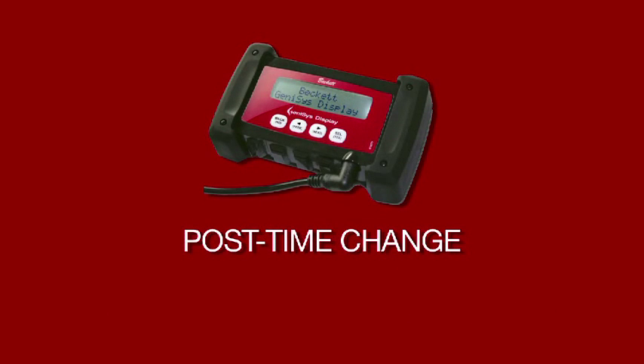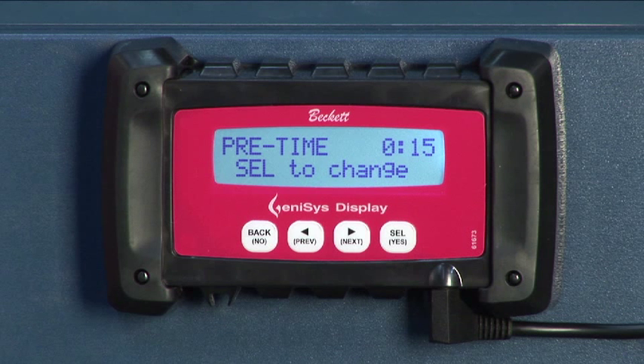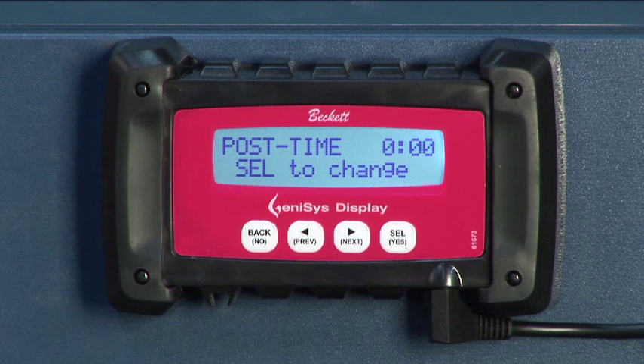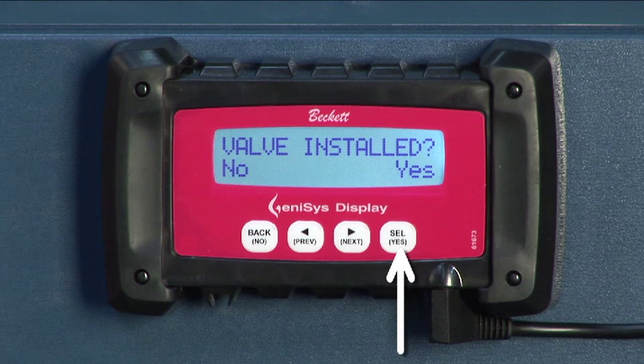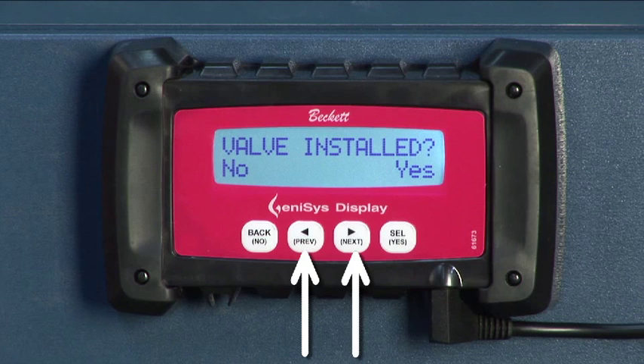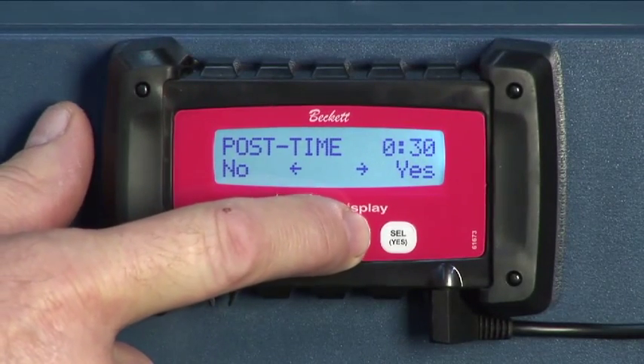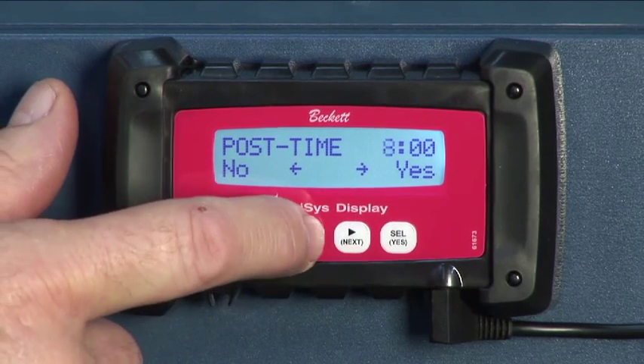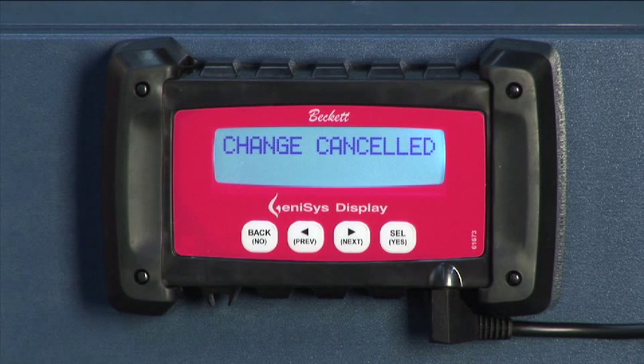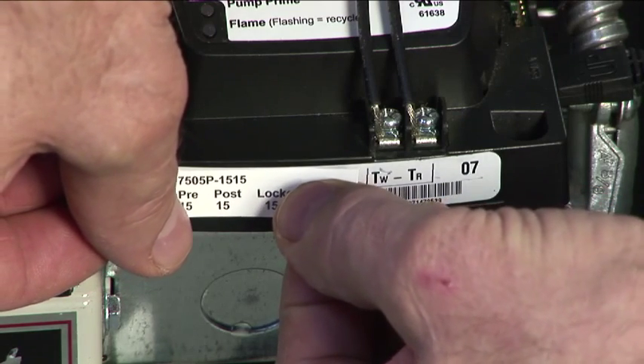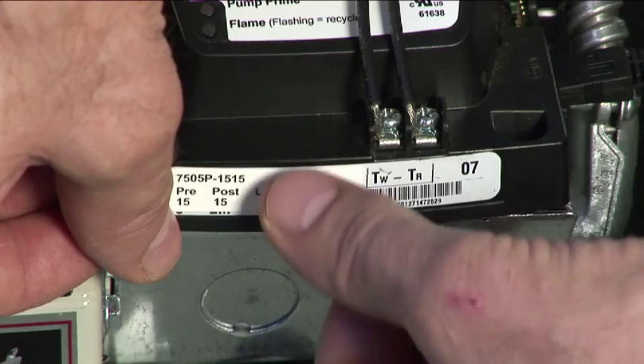The fourth functional category is post-time change. When we press next while on the pre-time screen, we'll go to the post-time motor-off delay, which will display the current setting. If the setting is 0, the display will again ask if a valve has been installed, which it needs to operate in post-time. In this example, the valve is installed. Press SEL yes, and use PREV and next to choose the post-time setting. Confirm the selection with SEL yes, or cancel the change by pressing back no, which will display 'change cancelled' and return to the initial post-time select to change screen. After changing the pre-time and/or post-time settings, apply the replacement labels over the existing labels, being careful not to cover up the barcode.